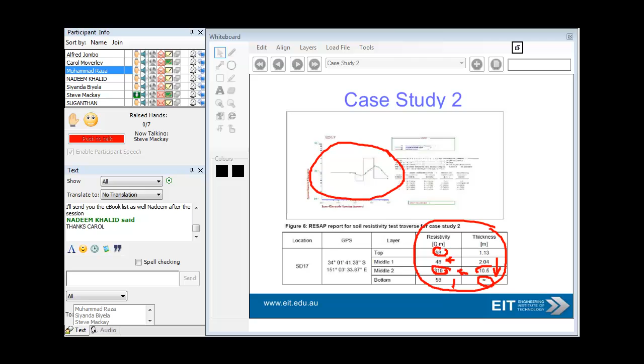The idea with case study 2 is use of the Wenner method, which I mentioned earlier, with probe spacing of 40 meters, 18-meter vertical electrode to penetrate the bottom layer, because there's some insulation from the top layer, and look at the depth and resistivity there. So plot the data at time of measurement and identify critical design parameters.